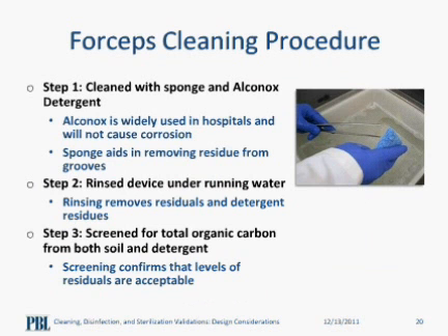So what we did first was clean the forceps with Alconox and a sponge, because Alconox is a detergent which is effective, widely used in hospitals, and more importantly, will not cause corrosion. The sponge helps remove residuals that may be trapped in the grooves of the forceps. Step 2 is very important.